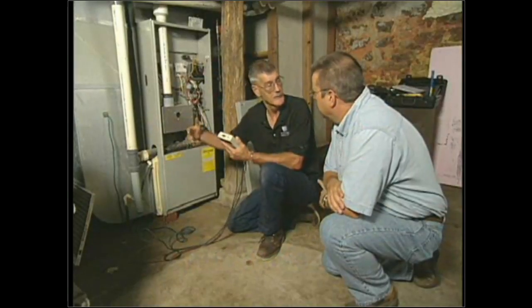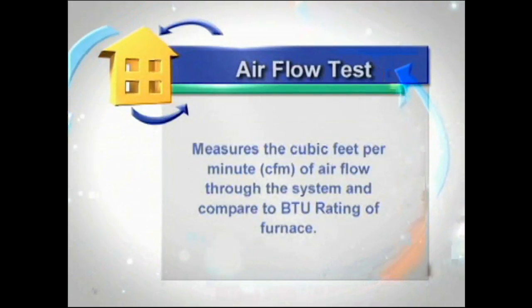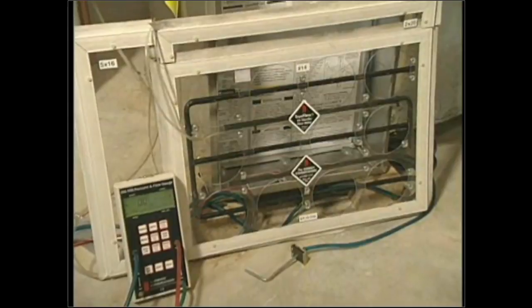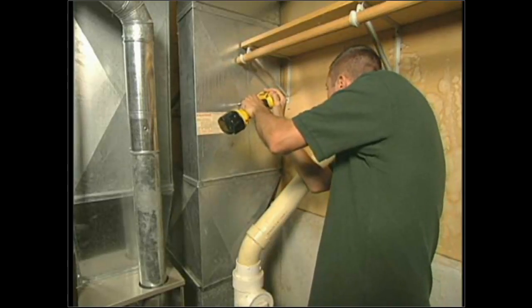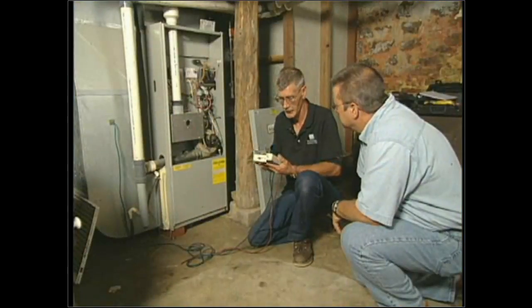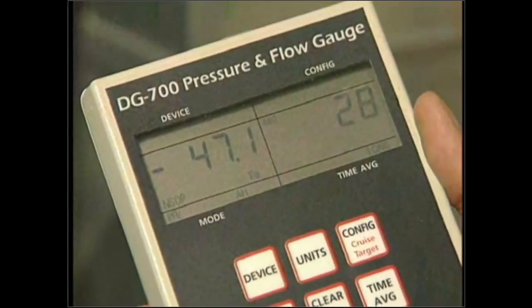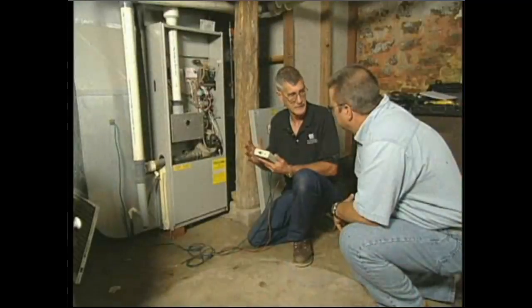What I'm finishing up here is an air flow test. I'm measuring the CFM of air movement through the system to match it to the BTU rating of the furnace. The equipment I use is a manometer and a flow plate. First, I select the location to put a hole for the static pressure probe into the return air system — about two feet up from the turn of the return drop. I turn the air handler on and measure normal static pressure, averaging over a period of time. This manometer averages hundreds of times a second and gives a solid average.